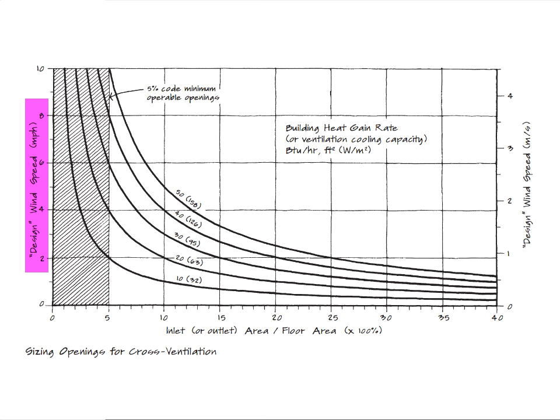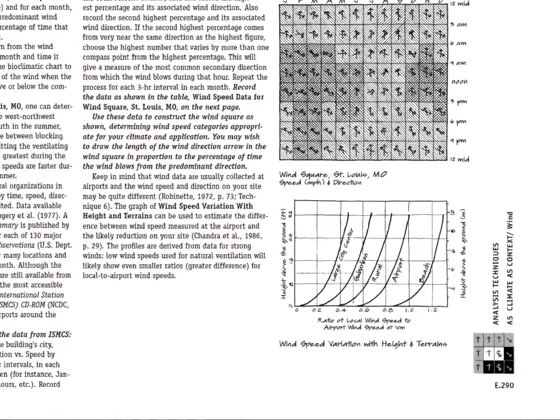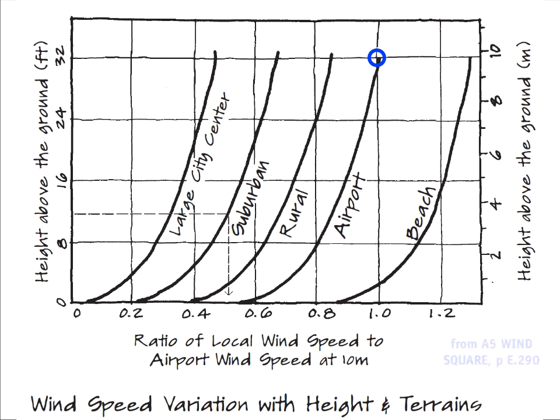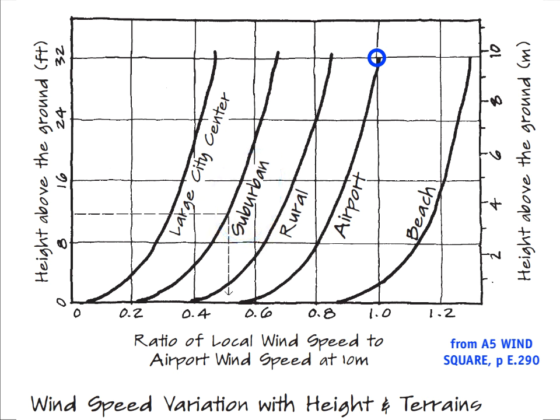The design wind speed is not necessarily the airport wind speed. You take the airport wind speed and modify it by a terrain factor. The airport measures wind at about 10 meters off the ground, giving a factor of 1.0 — 100% of the measured speed. Open beach locations may have more wind than the airport. Rural locations with trees and terrain, suburban areas, and large city centers each progressively reduce wind speed due to friction from buildings, trees, and terrain.